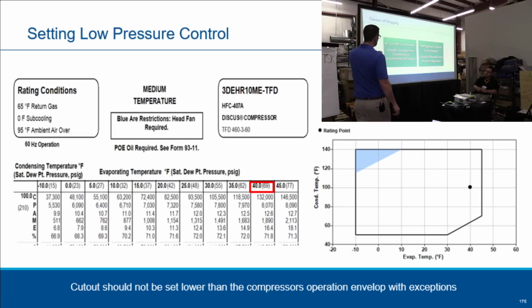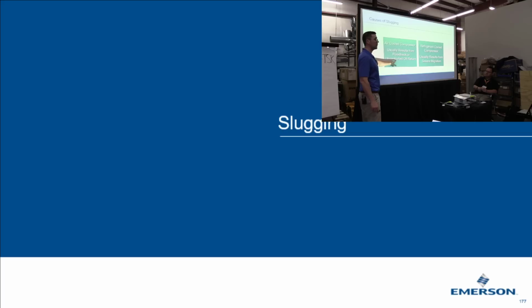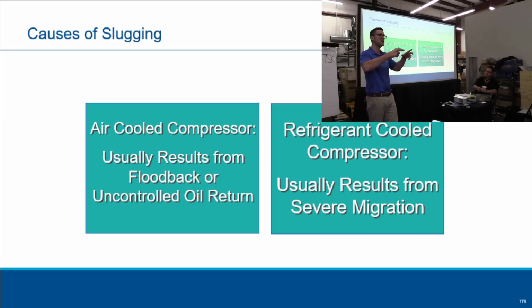Slugging in air-cooled compressors usually results from a flood back or uncontrolled oil return. Remember we talked about how the suction and discharge are right at the head. So if you've got lots of oil coming back and you're trying to compress that oil, what do you have? You have slugging, busted valves. Yeah, you have a bad day. With refrigerant-cooled compressors, it's from severe migration, right? That compressor fills up with a bunch of liquid refrigerant from migration, and when it starts up, that liquid refrigerant gets up into the cylinders and does some damage.